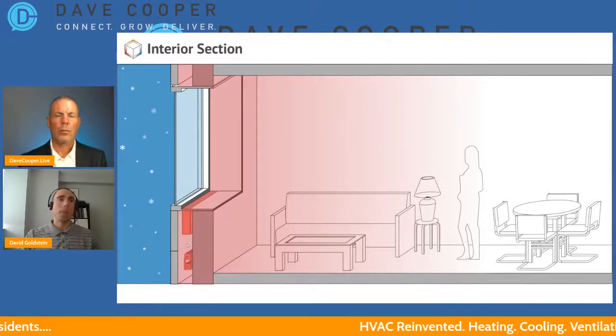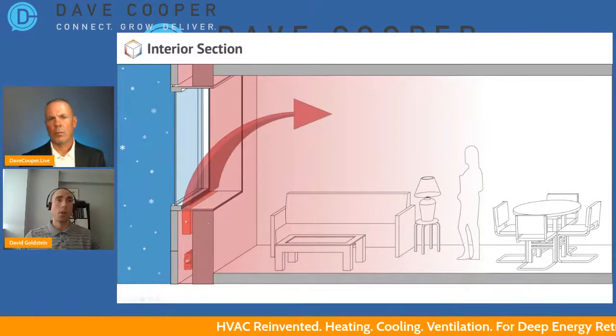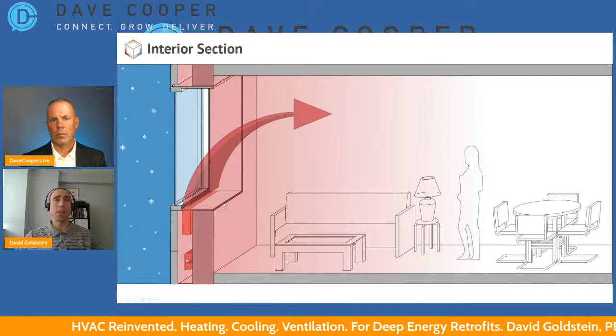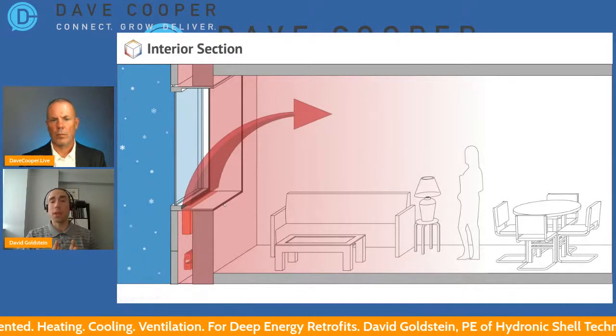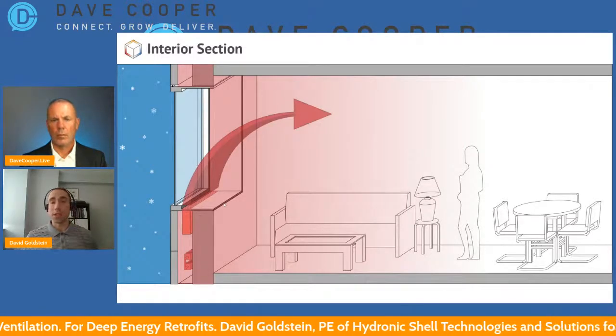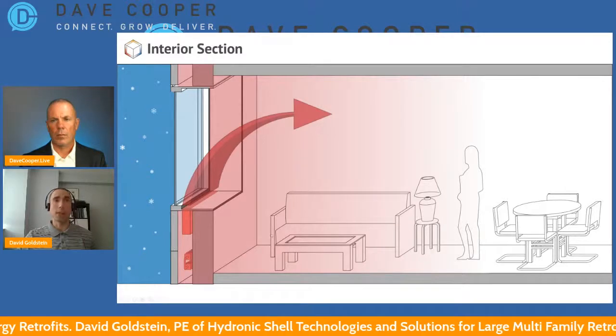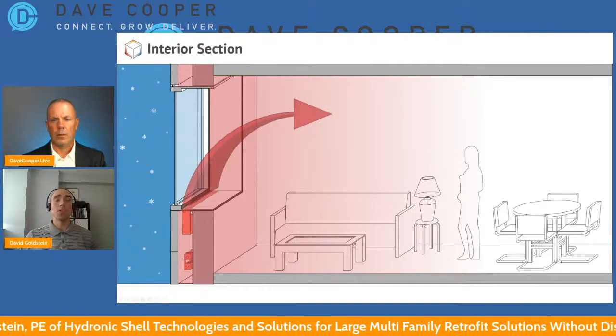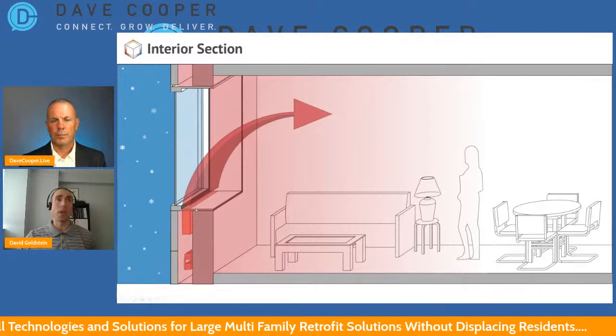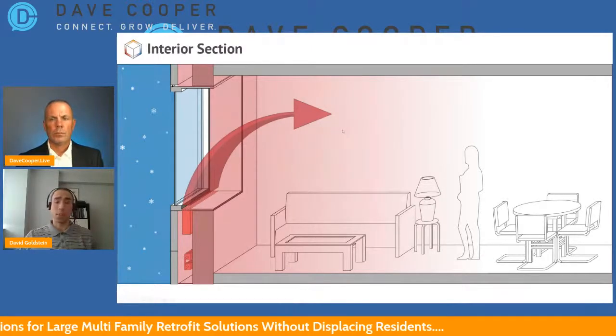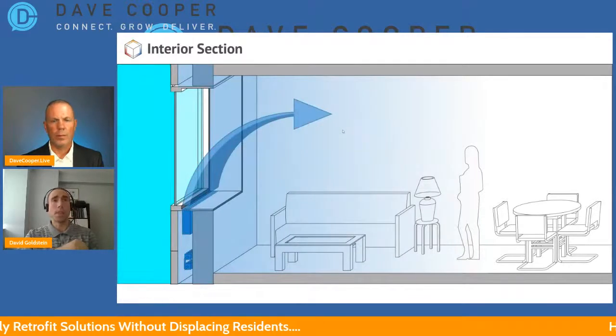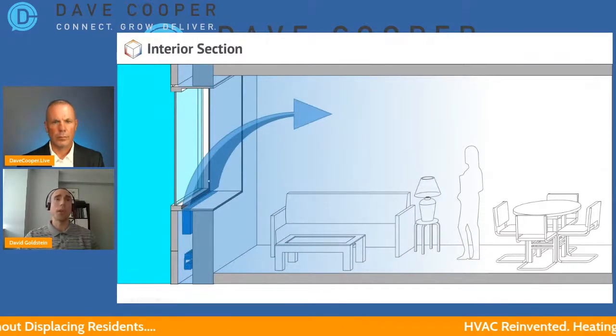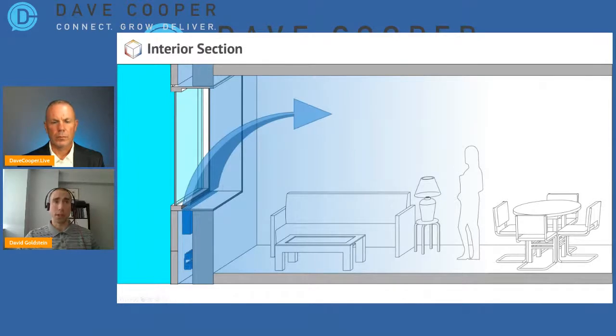But then we also have this component here, which is basically a custom fan coil unit that we designed that will also fit within that narrow cavity. That's going to do two things for us. One, it gives us additional capacity in case we can't get the full capacity from radiating through the wall. And it's also where we're going to introduce the ventilation air into the apartment. I mentioned it works for cooling as well, and it's really in cooling that we need that supplemental capacity from the fan coil unit, because we're not going to get that totally by radiating it through. So that's the main area where that fan coil unit comes into play.